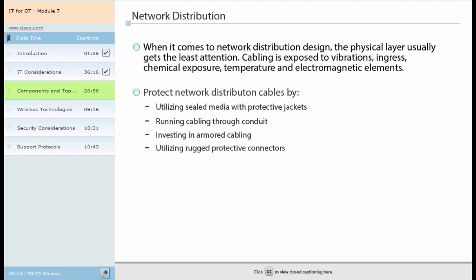When it comes to network distribution design, the physical layer usually gets the least attention. Unique environmental impacts in manufacturing are often overlooked. Consequently, a significant portion of network downtime is attributed to physical layer connectivity. Unlike the quiet, temperature-controlled environment of an enterprise office, a manufacturing floor is loud and harsh. On the equipment floor, gear and cable is exposed to mechanical vibrations, ingress of water, dust and liquids, chemical exposures, temperature, and electromagnetic noise. Therefore, network design should consider shielding network distribution cables by utilizing sealed media with protective jackets, running cabling through conduit, investing in armored cabling, and utilizing rugged protective connectors.